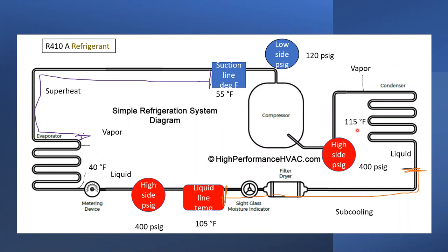The SEER rating was developed in the 2000s when new air conditioning refrigerant was coming out that's better for the atmosphere. We don't want to leak refrigerant into the atmosphere, and we want to get more bang for our buck. So the SEER rating is about developing a unit that will run more electrically efficient. If you start out with a 12 SEER unit and you go up to a 20 SEER unit, your 20 SEER unit is going to have a bigger condenser. The tonnage is going to be the same. It'll be a 2-ton unit, but with more surface area so you can get more heat exchange at less electrical energy consumption. That's what SEER, seasonal energy efficiency ratio, means. It's measuring the amount of electrical consumption that the unit is going to use, and a higher SEER rating is going to give you more efficiency.